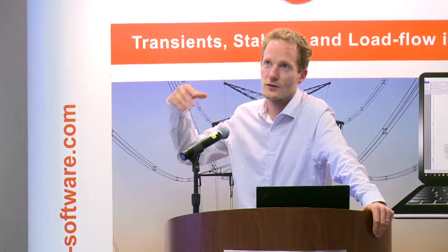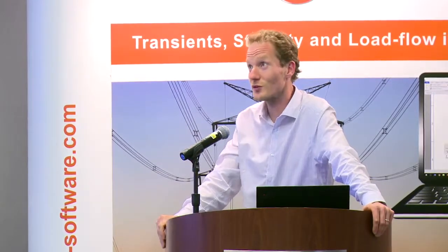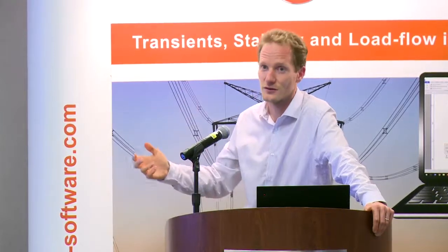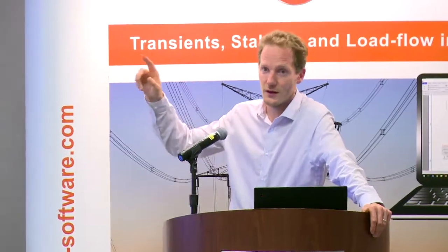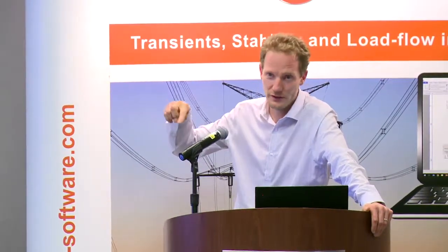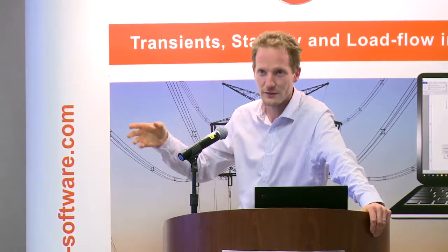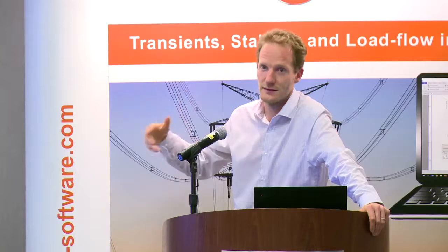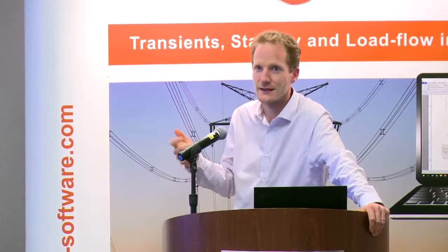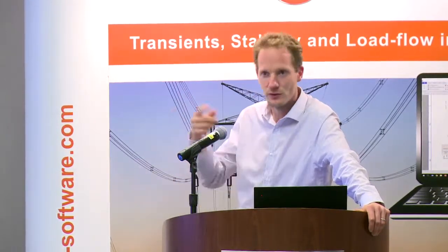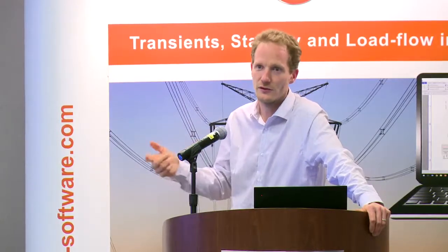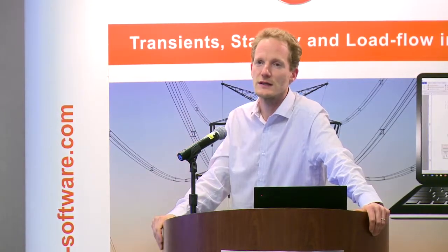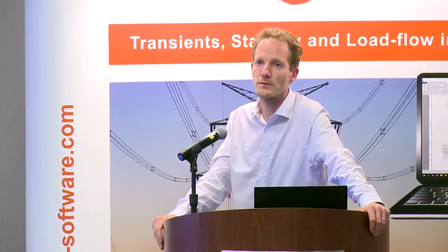Obviously, there could be some solution to automatically initialize this system, but you need to initialize the control. You need to do a load flow in the DC part and a load flow in the AC part. That has been done, but there is nothing here that is automatic, so you have to develop some script to do this automatic initialization. It's a really complex question.